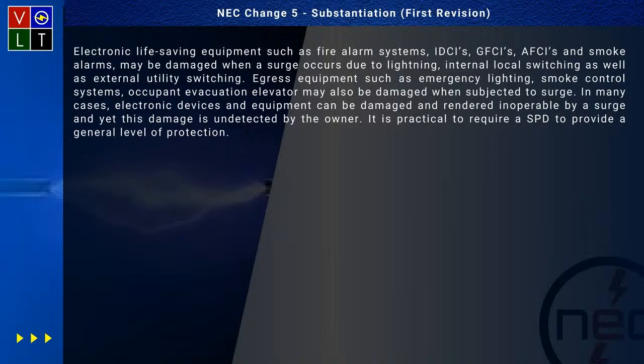They're going to tell you here that electronic life-saving equipment such as fire alarms, they just go through your AFCIs, your GFCIs, all that, and it says may be damaged when a surge occurs due to lightning, internal local switching, as well as external utility switching. What they're basically telling you is you're putting this surge protection on because let's say you got a lightning strike and you blew up your fire alarm or something like that, then all of a sudden you've got a problem because if something happens, that unit's not working anymore, is it?